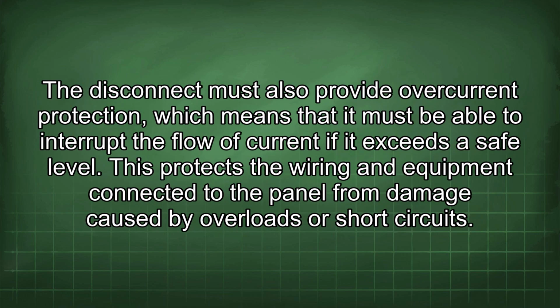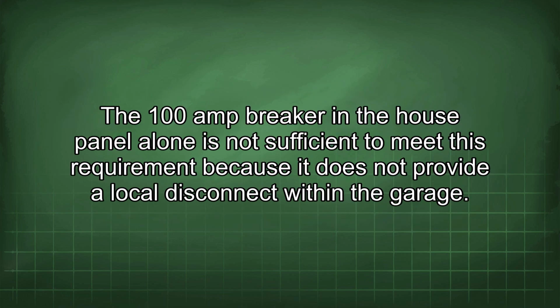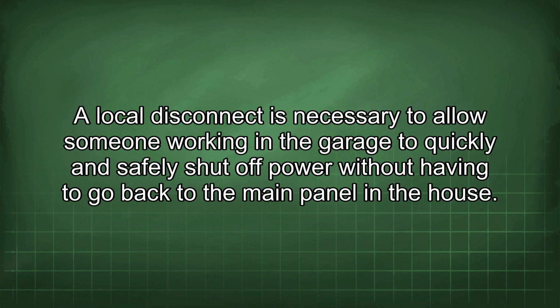The disconnect must also provide overcurrent protection, which means that it must be able to interrupt the flow of current if it exceeds a safe level. This protects the wiring and equipment connected to the panel from damage caused by overloads or short circuits. The 100 amp breaker in the house panel alone is not sufficient to meet this requirement because it does not provide a local disconnect within the garage. A local disconnect is necessary to allow someone working in the garage to quickly and safely shut off power without having to go back to the main panel in the house.